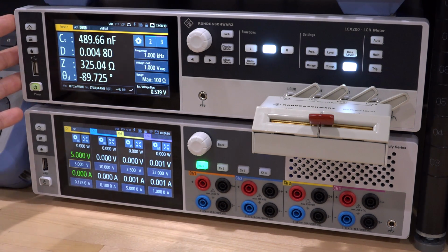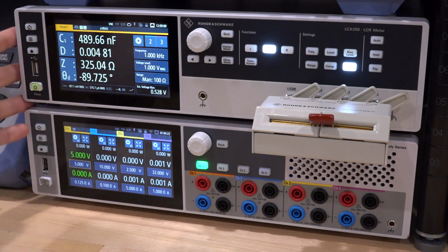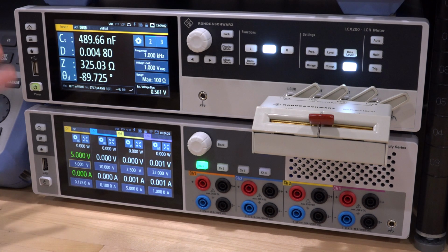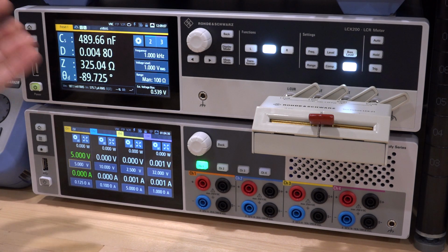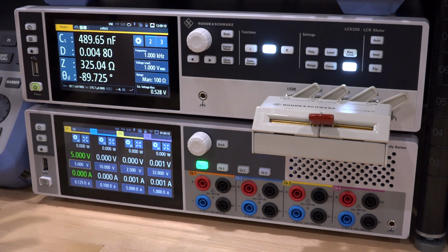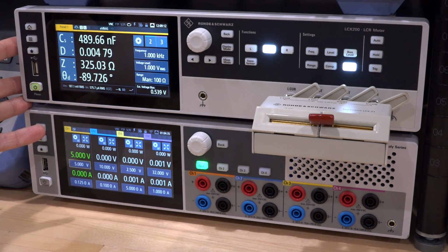Now, if I were to design, let's say, an LCX300 version above this one, I would incorporate things like a 2-quadrant source for both current and voltage, whether it's internal or external, and make sure that the auto ranging is a little bit faster, perhaps with overlapping regions and even in solid state if possible, to allow the measurements to be even quicker so that you don't have the relay delay, of course, that comes into it. There's a lot of improvements that can, of course, be made, but in terms of the software, you can do things like resonance detections and being able to find faults in LC circuits or power supplies built in to various personalities. And I think that's probably what they're planning, because this platform with the operating system gives you so much flexibility in future designs, of course.